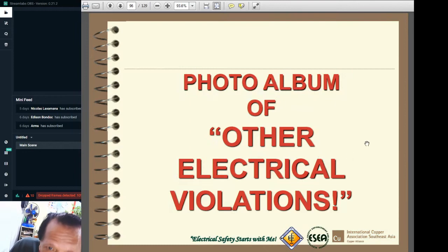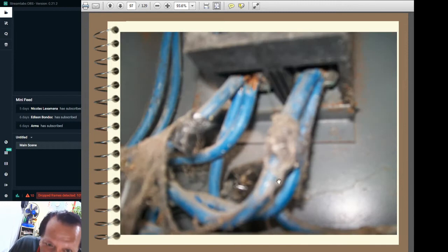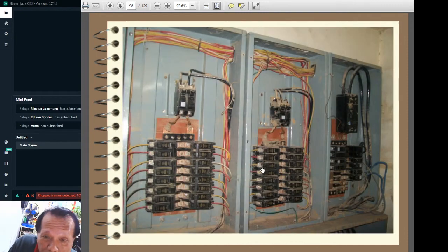So here is a photo album of some violations again, just to remind us. Here is a dirty installation. It's possible that dirt would come in contact with electricity, and during the rainy season this dirt could become moist and therefore would cause grounding or an electrical short circuit. Here is a picture of an electrical panel board which was submerged in flood waters during typhoon Ondoy in 2009, and it was never cleaned before it was energized or used again. So again, lack of maintenance is the problem here. Nobody did the real maintenance before they were put back into service.